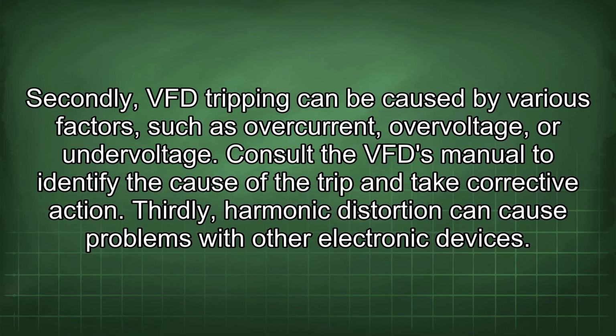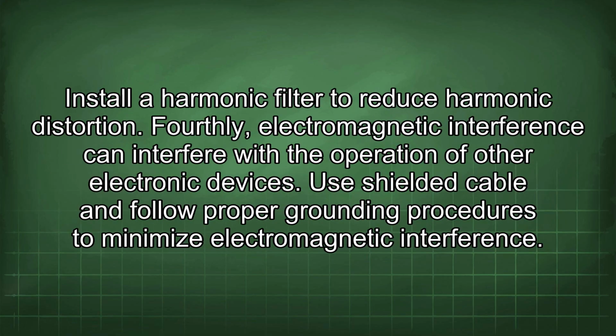Thirdly, harmonic distortion can cause problems with other electronic devices. Install a harmonic filter to reduce harmonic distortion. Fourthly, electromagnetic interference can interfere with the operation of other electronic devices. Use shielded cable and follow proper grounding procedures to minimize electromagnetic interference.